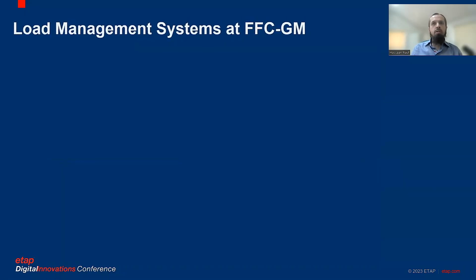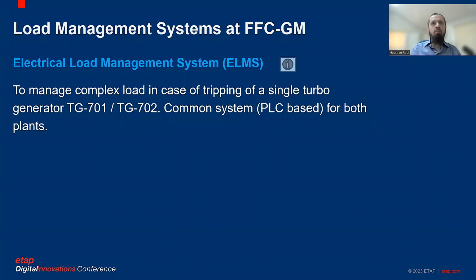So for the load management system at FFC GM, there were two systems. One is the electrical load management system, or ELMS, which is the topic of today's session. This system manages complex load in case of tripping of one turbo generator. It is a PLC-based system. It is common for both plants, that is, it is connected to the loads of both plants.